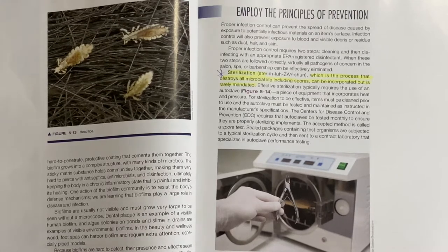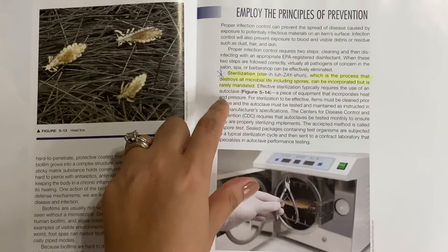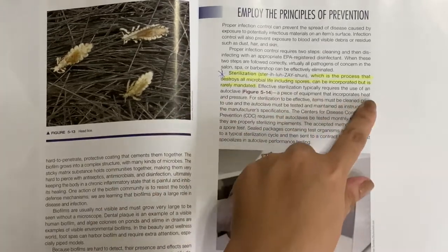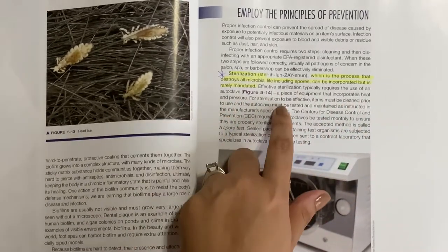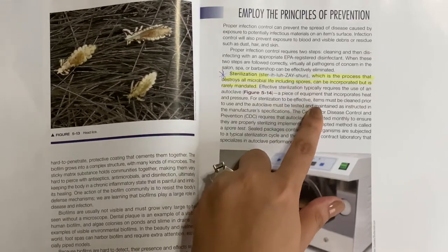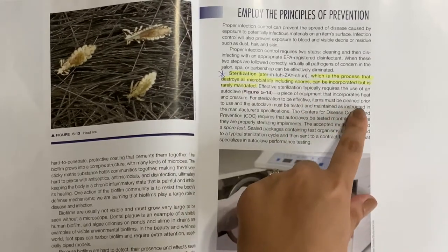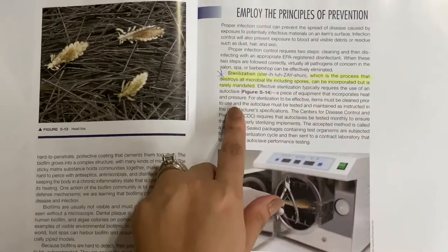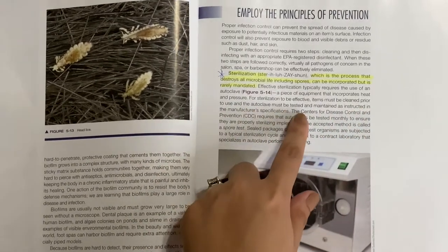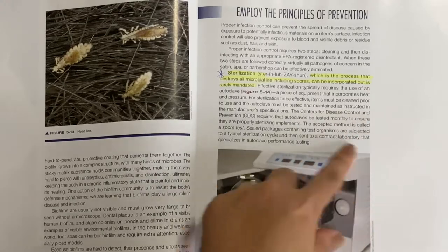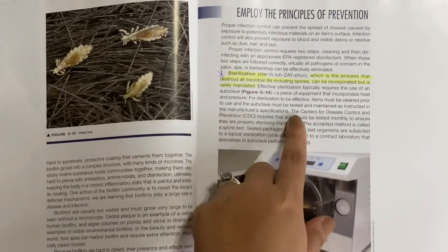Sterilization is the process that destroys all microbial life, including spores. It can be incorporated, but is rarely mandated. Effective sterilization typically requires the use of an autoclave, a piece of equipment that incorporates heat and pressure for sterilization to be effective. Items must be cleaned first, prior to use, and the autoclave must be tested and maintained as instructed by the manufacturer's specifications.